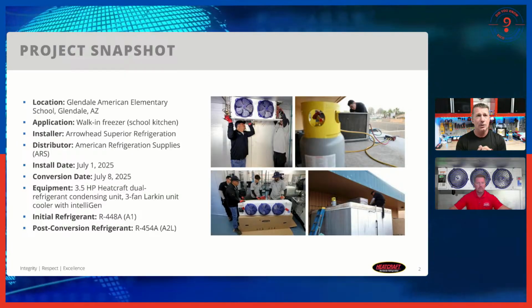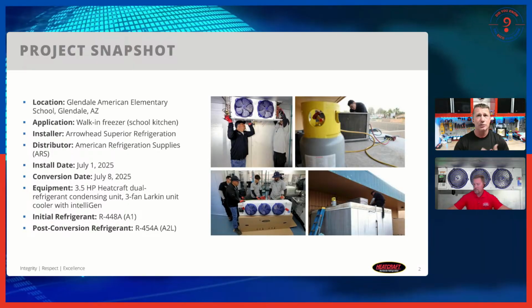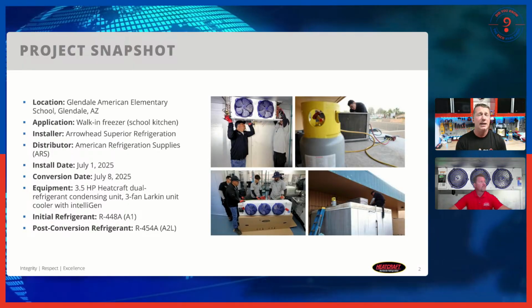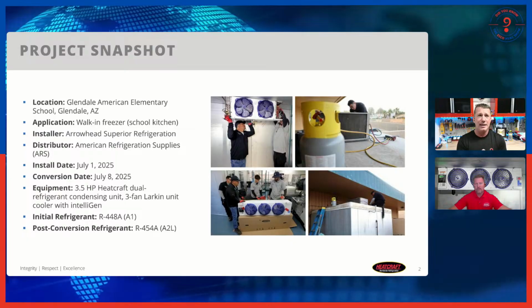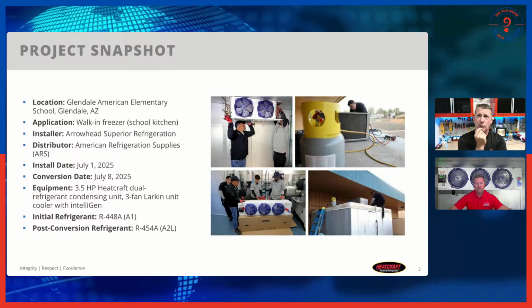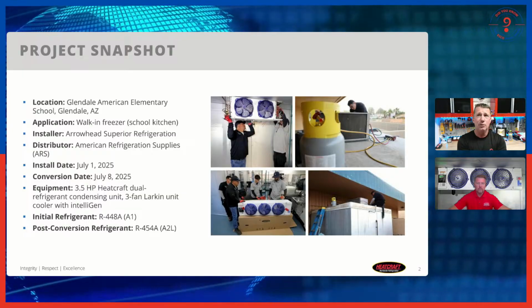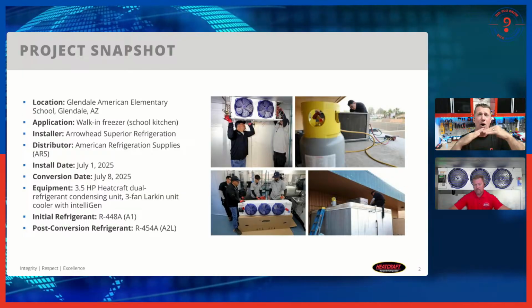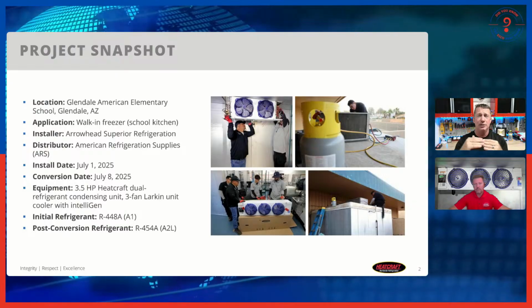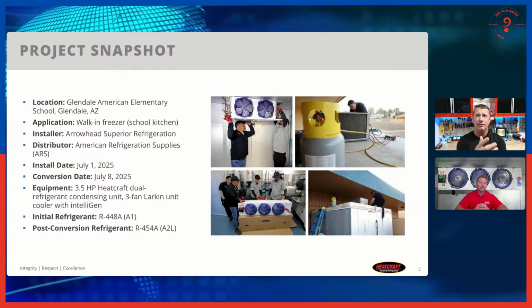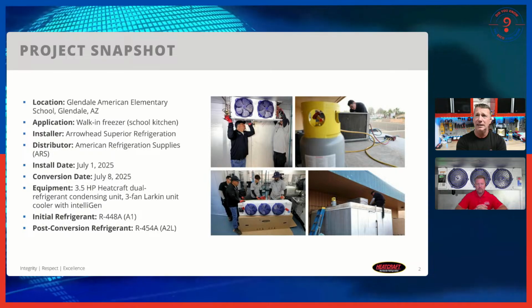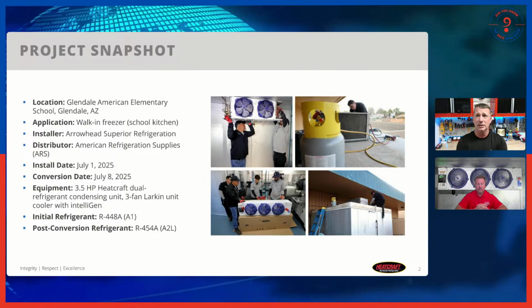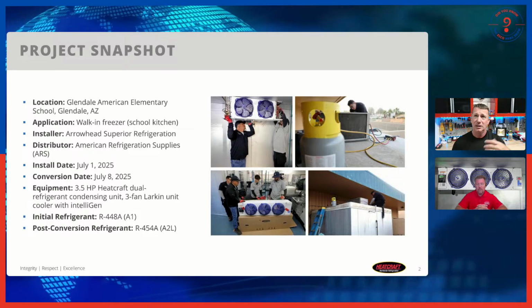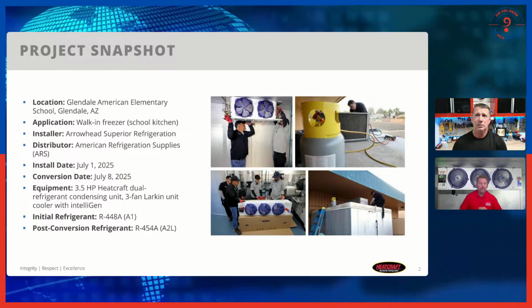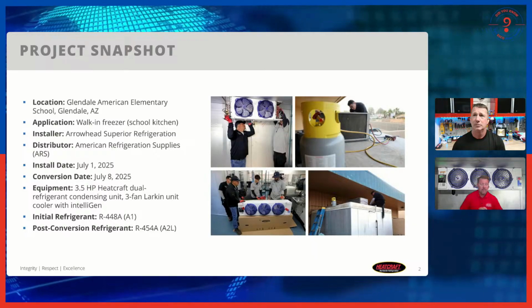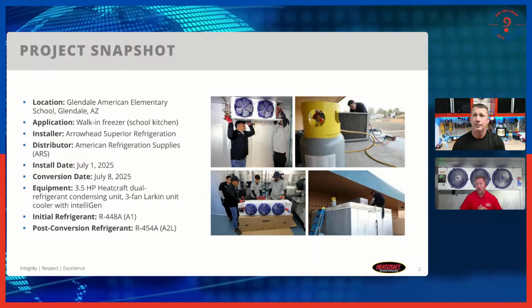It's really cool that you're using the 454A. We've been discussing here recently the difference in refrigerants. We've gone through a lot of refrigerant chemistry. In that 454A, because people go, wait a minute, is that close to 454B? Well, yeah. So we actually have 454A, B, and C, all with different proportions of R32 and R1234YF. And the 454A is turning out to be a really good solution in these low temp applications. And again, this is my first experience with an actual real world case study.